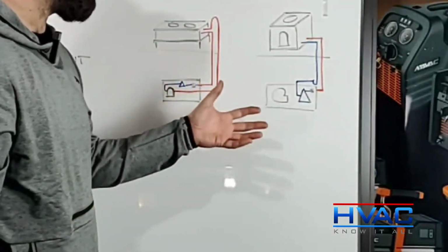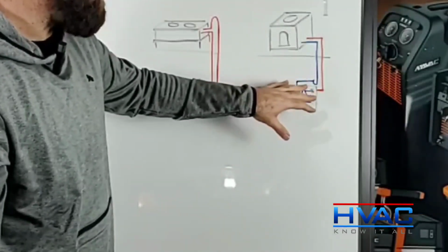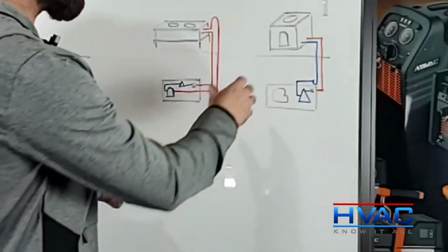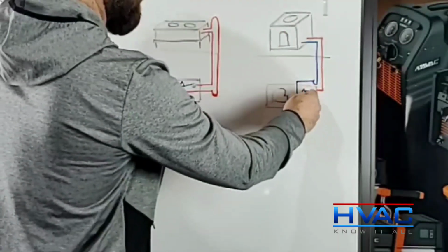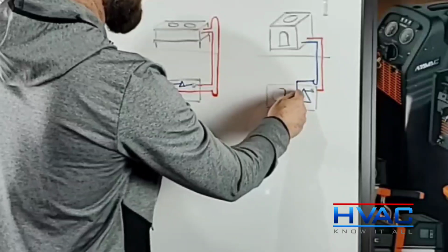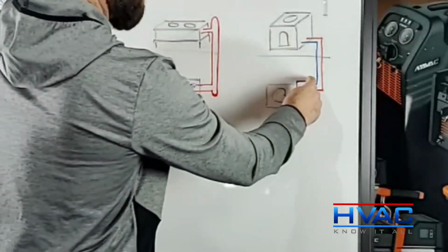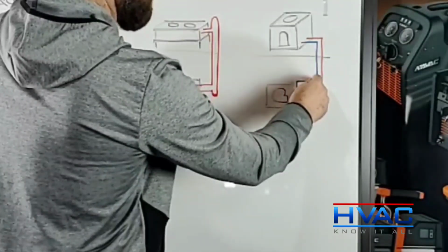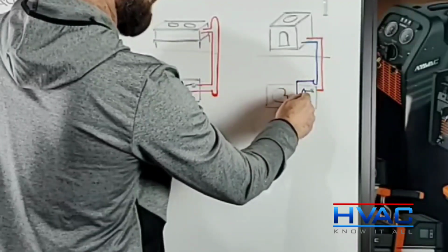The other scenario here is I've drawn a condensing unit on a roof and an air handler down inside. Obviously we are going to leave the condensing unit and drop down. The liquid line is going to come in through the metering device and evaporator. And from the evaporator, there's a riser back up. At the bottom again, I have trapped that, because we want to trap the oil right there so we're not logging the evaporator.